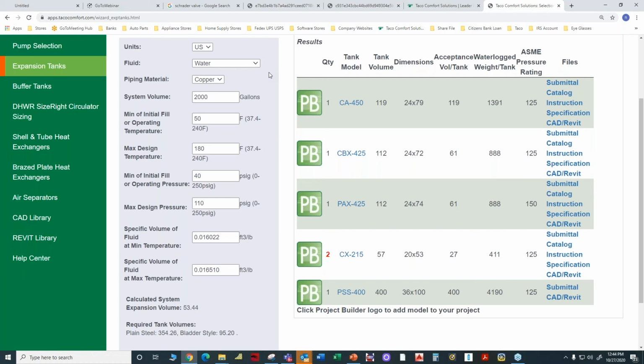If I move the expansion tank in the mechanical system, right now I have it on the first floor of the building. If I should move that up to the top floor of the building, and again, I'm oversimplifying my diagram, my pressure at the top of the building, we said, was 7.5 pounds, so it's no longer 40 pounds. Now, make a mental note that our tank size is 95 gallons and our expansion is 53 gallons.